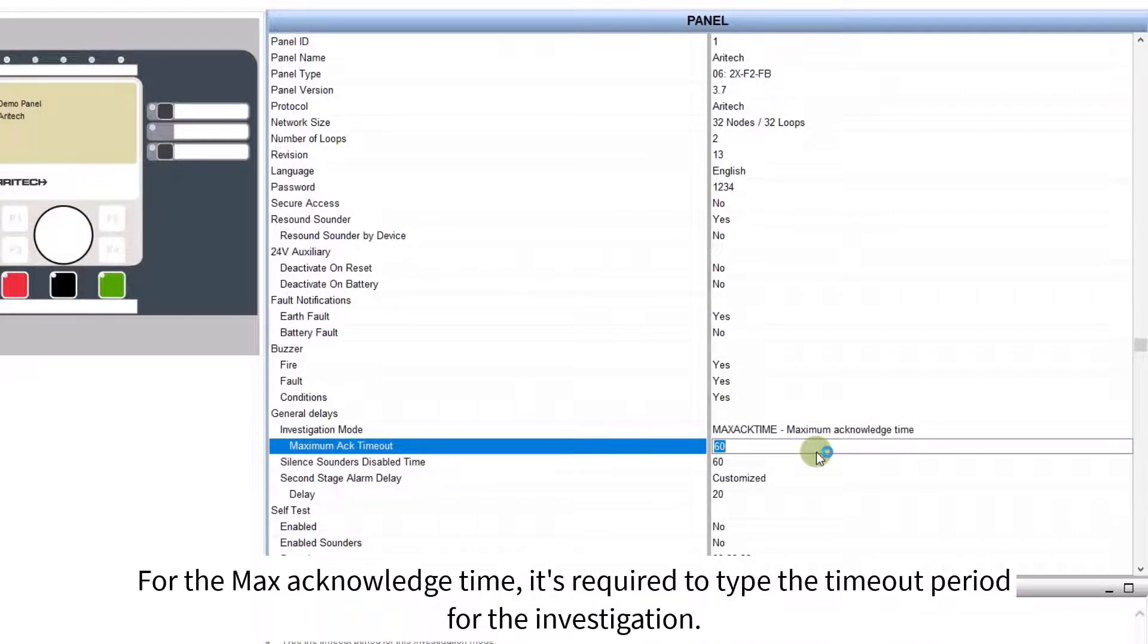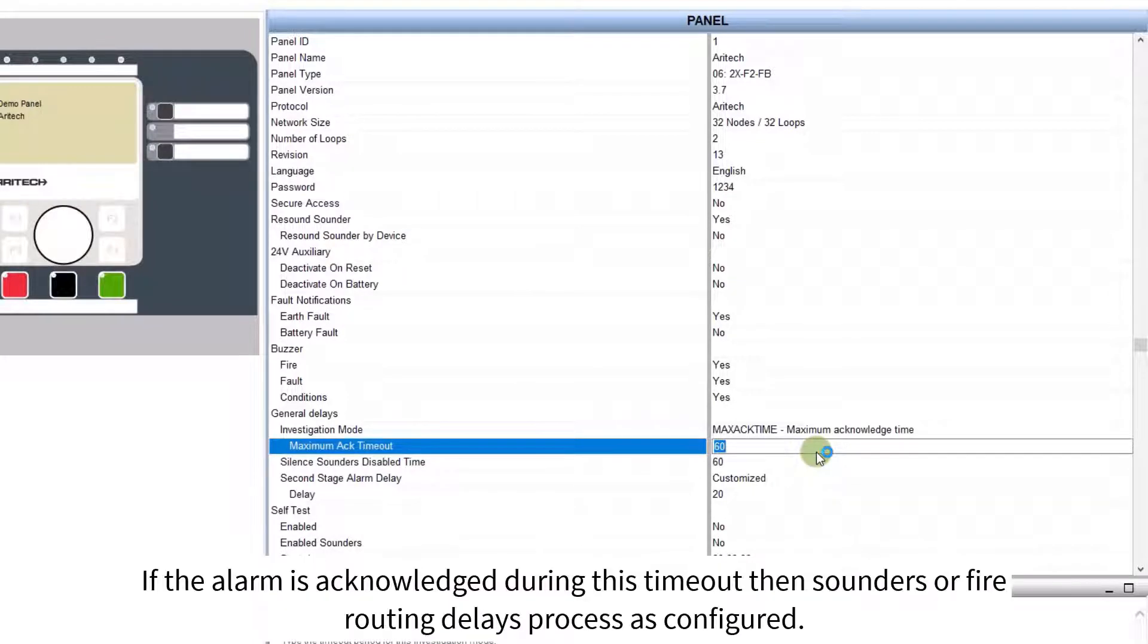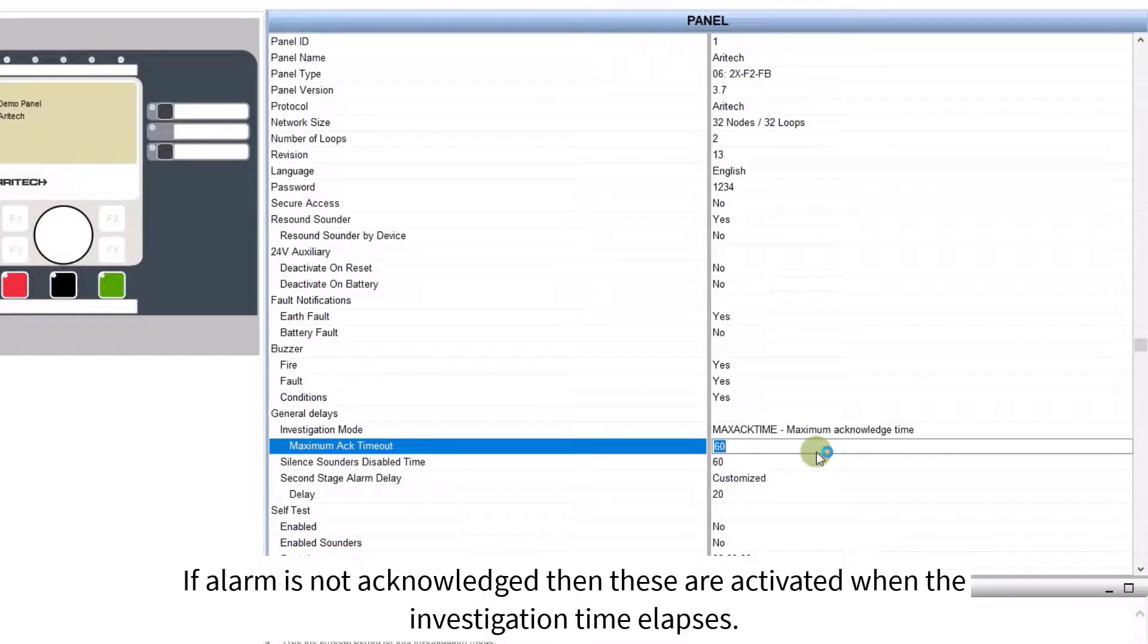For the max acknowledge time, it's required to type the timeout period for the investigation. If the alarm is acknowledged during this timeout, then sounders or fire routing delays process as configured. If alarm is not acknowledged, then these are activated when the investigation time elapses.